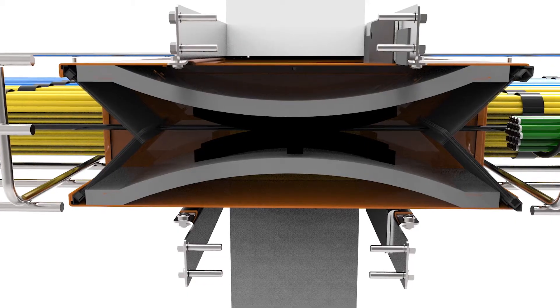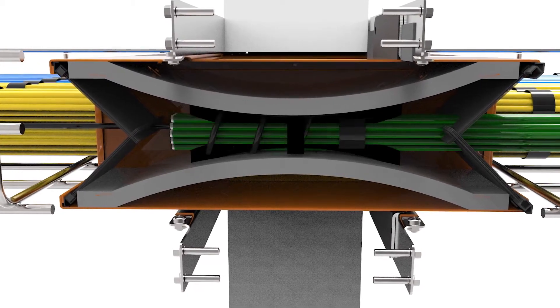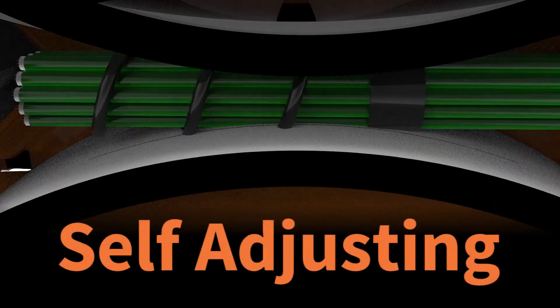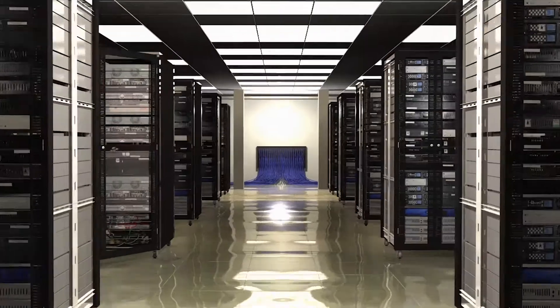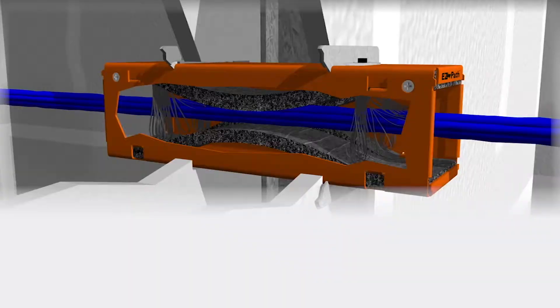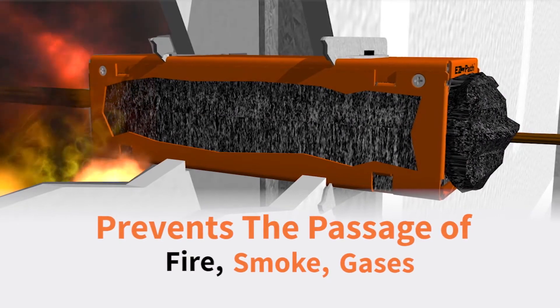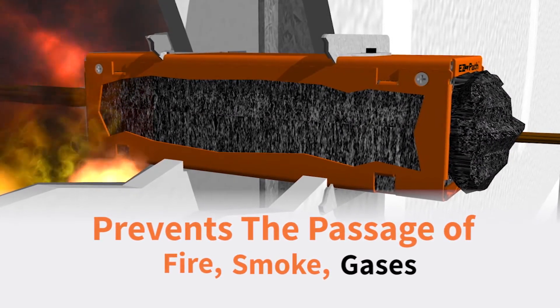The EZ-Path system consists of an enclosed, heavy-gauge galvanized steel channel lined with self-sealing and self-adjusting intumescent pads. These patented, state-of-the-art pathways are engineered for rapid expansion when exposed to fire or high temperatures, preventing the passage of fire, smoke, and gases.